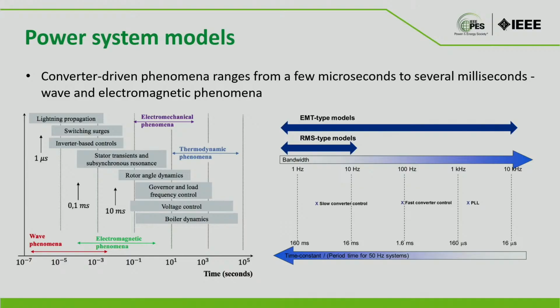If you have a lot of IBR in the grid, which has a lot of high frequency switching devices, inverter based sources are basically high frequency switching devices, IGBTs, which often have the PLL and fast converter control. So DC link controls are really fast controls, not necessarily slow controls. Then RMS model wouldn't be able to capture those controls and their impact on the system. That's where you need to go with the EMT model, because it has the capability to capture those fast dynamics associated with IBR.